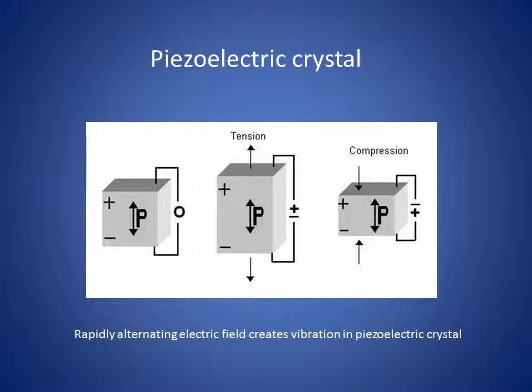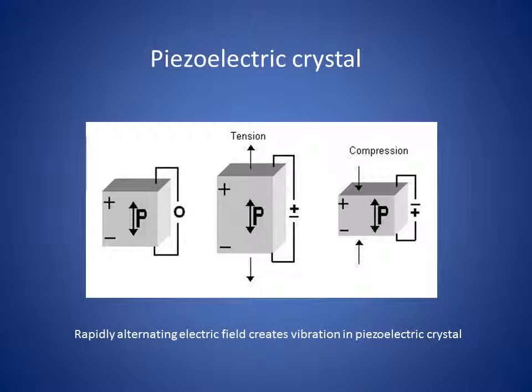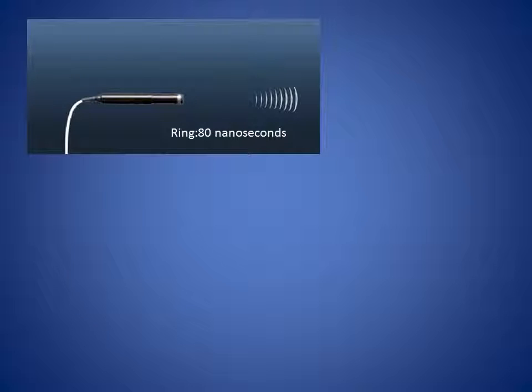If the electric field is reversed, the effect on the material is reversed. If the electric field keeps reversing, the material alternately contracts and expands, so a rapidly alternating field causes the material to vibrate. In an ultrasound probe, a rapidly alternating electric field is passed across an array of crystals, causing them to vibrate and emit a high frequency sound wave.